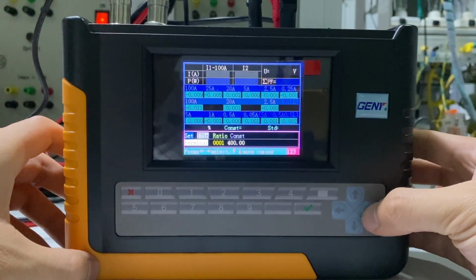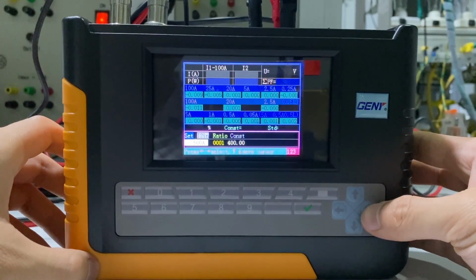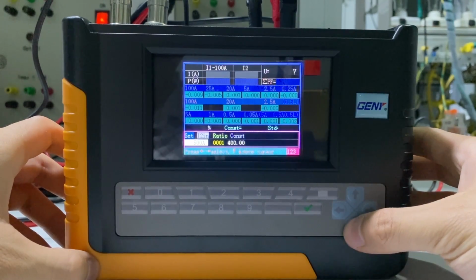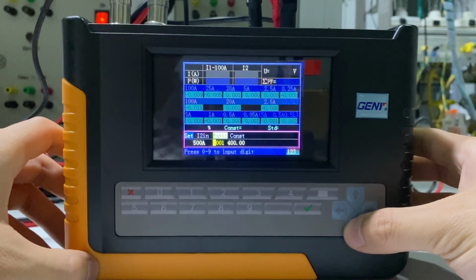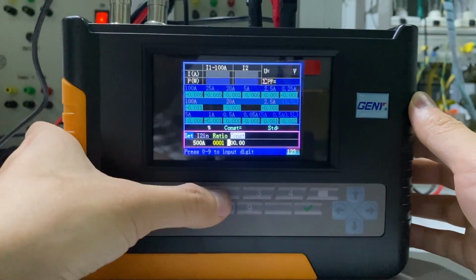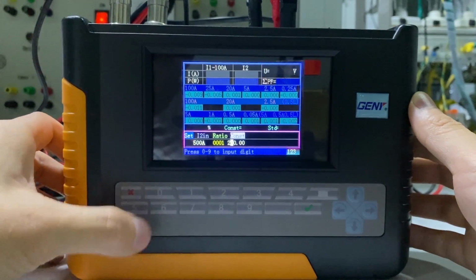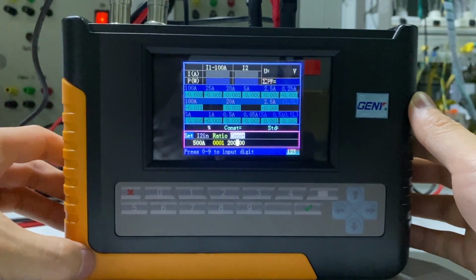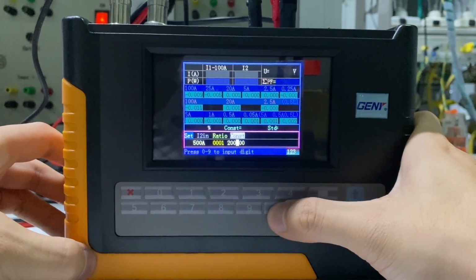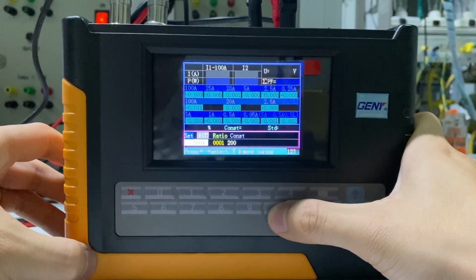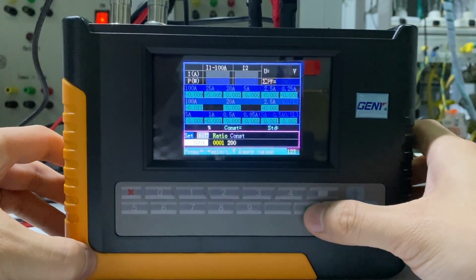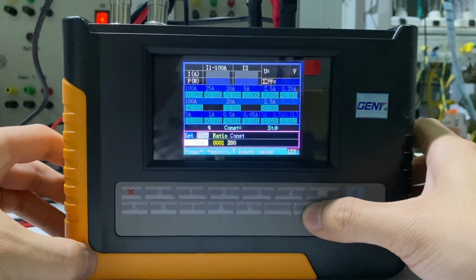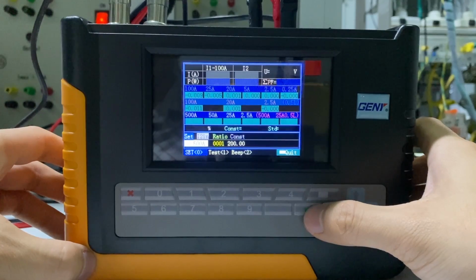Use the cursor key to select the input option. It defaults to 100 ampere, so there is no need to select any input. Input the constant of an external standard meter. The reference meter has a constant of 200 at 100 ampere. We can delete the rest of the characters. Press the green button to confirm the setting.